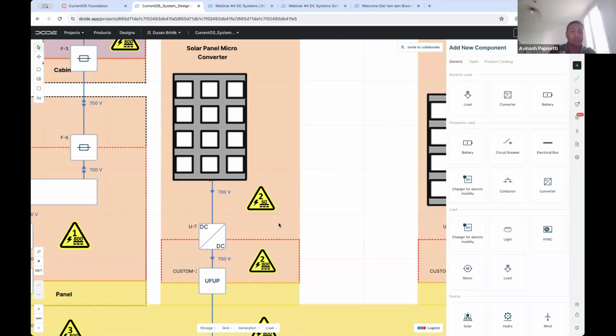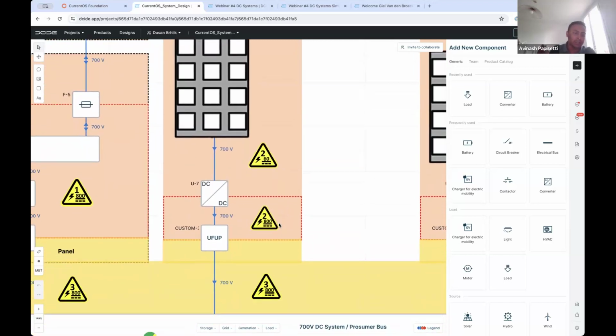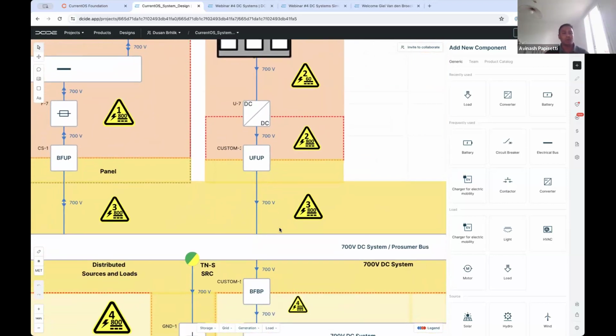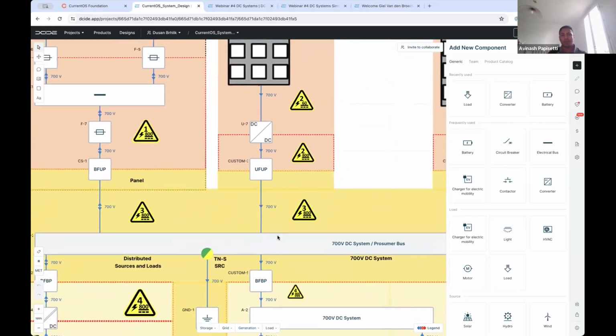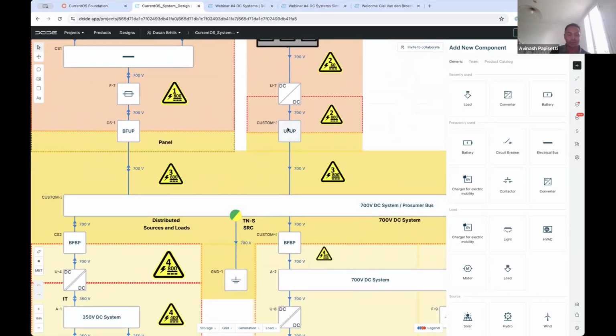More above zone 2 is zone 3. Zone 3 is an area where you are very well protected. You have something like ultra fast protection, which is solid state protection, where the products can trip in microseconds. So it's a kind of safe area, but you have no clue where the power flow is coming from and going towards. It is a bus which is protected, but still there is a bidirectional flow of energy, a combination of sources and loads coupled to the same bus.